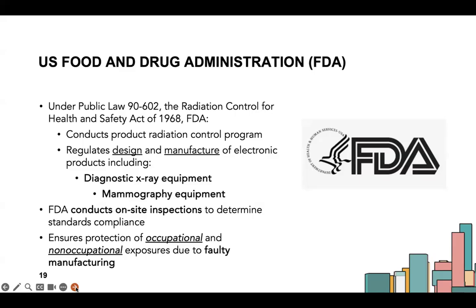but also the equipment has to be up to a certain standard because you are trying to detect the smallest lesions for early detection of cancer, and you have to have specific equipment. It has to be calibrated specifically. So FDA is very involved in mammography, very strict on those regulations. They can come in and do an inspection if your equipment is not up to standard or is not passing quality. They can shut your mammography program down.